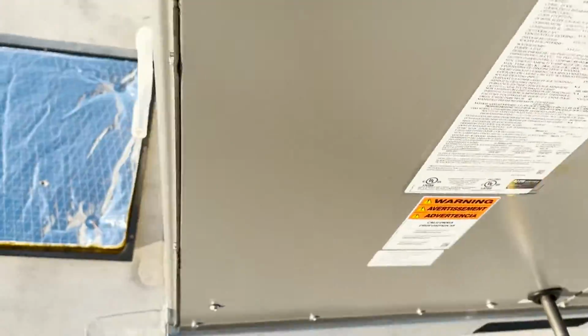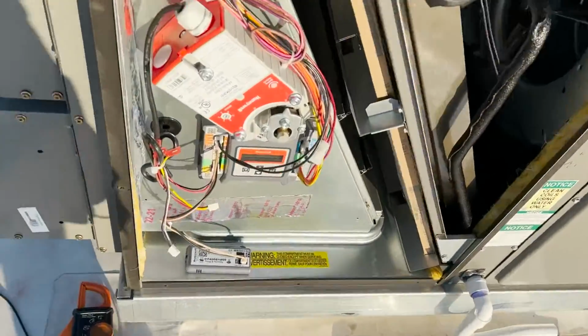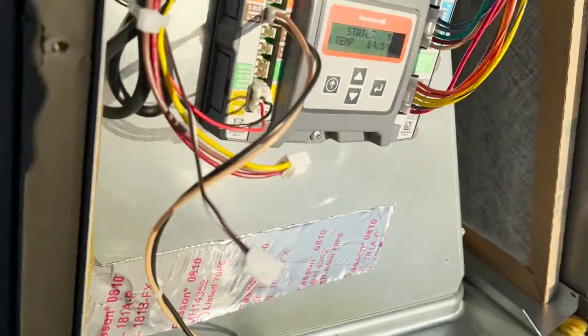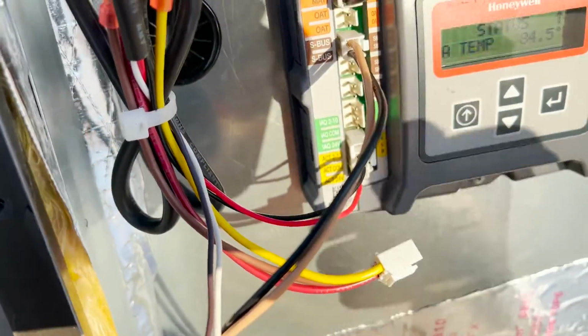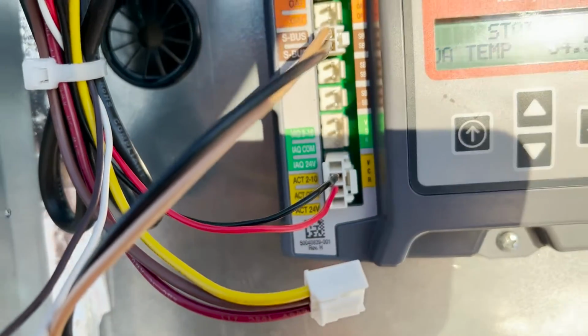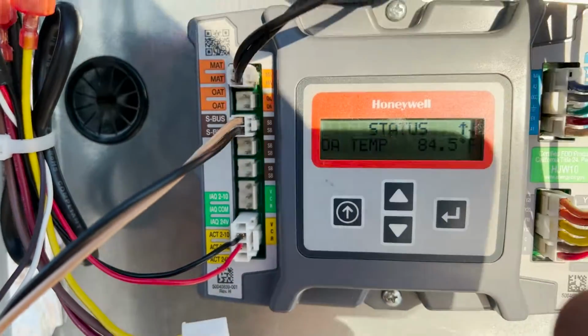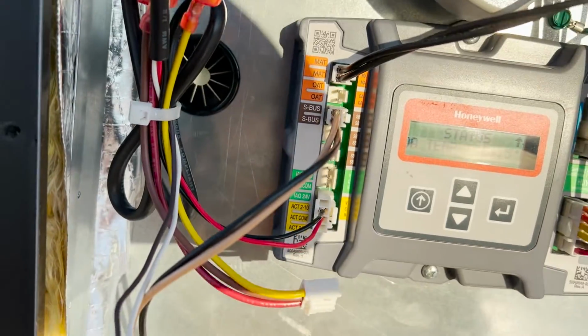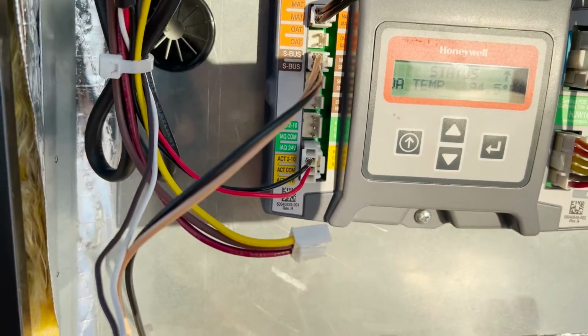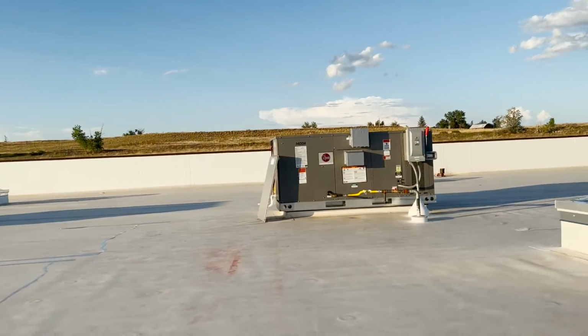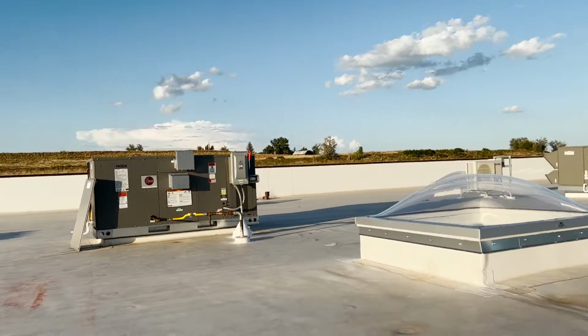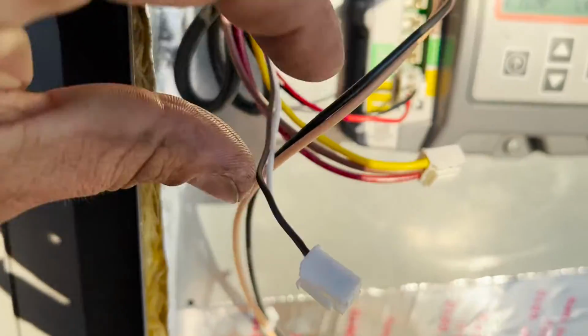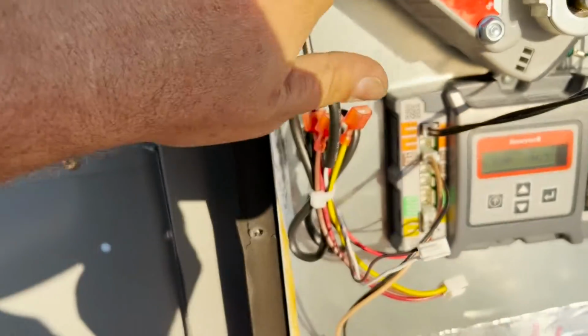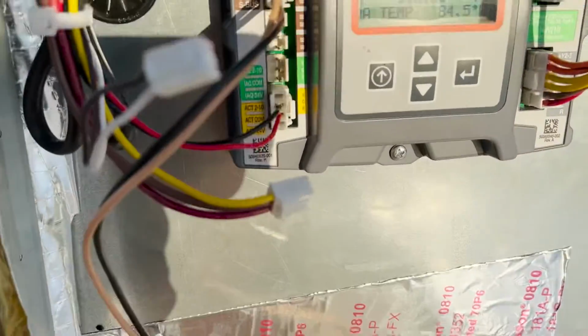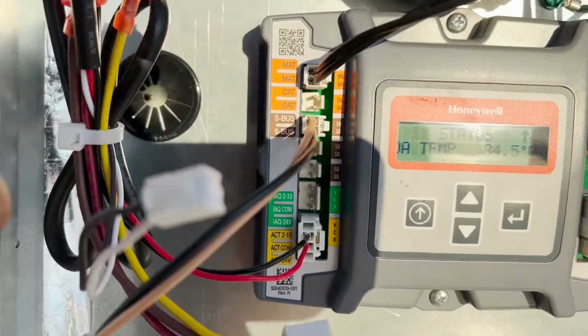All right, I'm getting close because I can get this to read sometimes. Okay, 1400B. The issue is that it's not reading the outside air. So when it doesn't read the outside air, I got my needle points out. I'm not even gonna try to chopstick it. But between any of the SB terminals, when I'm getting no reading, it's 0 volts DC or like 0.002. Like over there, I get 18 volts DC all day, all the time, no problem. Pulling everything off, mainly the only other thing in is this, and I start to get my 18 volts DC back, and we can start to read that.